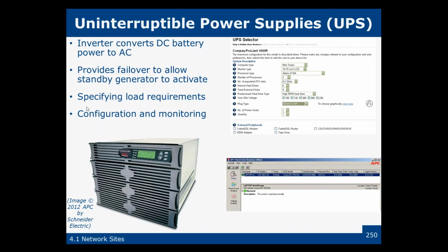But you need to, on the UPSs, maintain checks on them, because it's pretty embarrassing when the power goes off and your UPS battery's dead and everything dies. And that does happen. It has monitoring. The UPSs, the standby power supplies, the generators can run things for a long time. UPSs generally are not designed to run the network for a long time. They're designed to allow you to do an orderly shutdown, because it really doesn't do you a whole lot of good to keep the servers up if everything else is down.